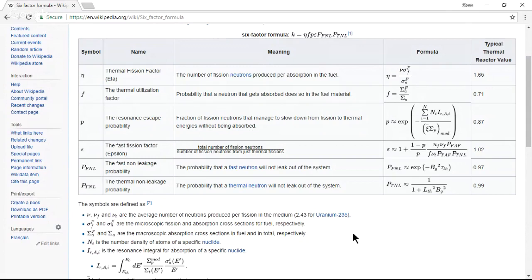So what's going on here is that the control rods of the reactor don't actually control reactor power. That's kind of a misconception. They do at some point during startup, when it's called the point of adding heat and in some criticality range. But at working conditions, when the reactor is actually at criticality, meaning the reactivity that Joe was talking about, the K effective, K-E-F-F, from one generation to the next generation, there is no change on average of the amount of neutrons in the core. So in other words, once you've got the reaction going, it's not really a change. We're talking about generations: an atom splits, neutrons come out, they hit the next atoms. That's another generation, right?